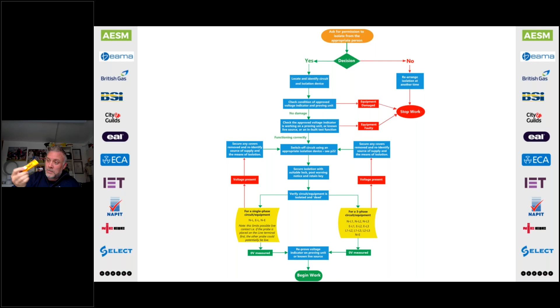There are many lock-off kits. This is an example one for an MCB or a circuit breaker, and you're going to put the appropriate lock-off device on. If you're using things like MCBs, for example, you might use different devices. So there's a variety of devices and lock-offs you can use, even ones for BS88 fuses for the old MEM and Eaton boards and the old bill boards, or the red spots as people call them. There's a lot of devices you can use to lock off and make safe. We're going to secure that, obviously, with notices. So padlock, key, notice. Notice the padlock only has one key, so no one else can energize the supply. So we're going to secure those to our points of isolation.